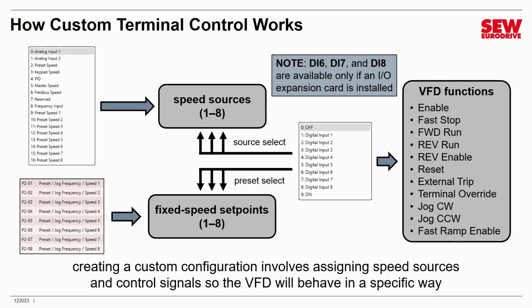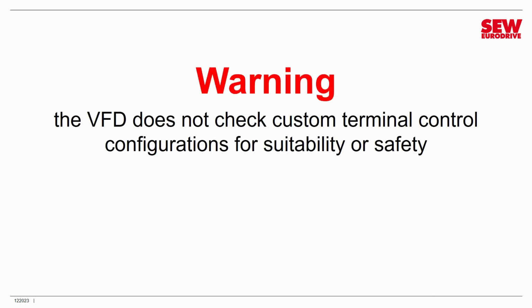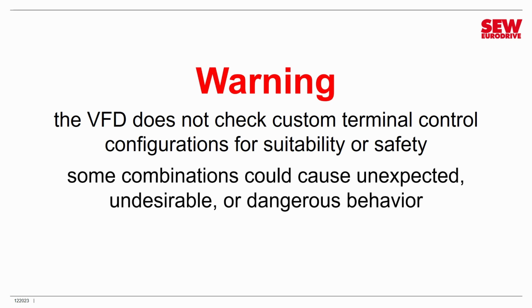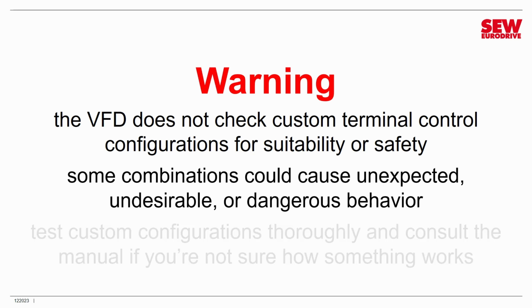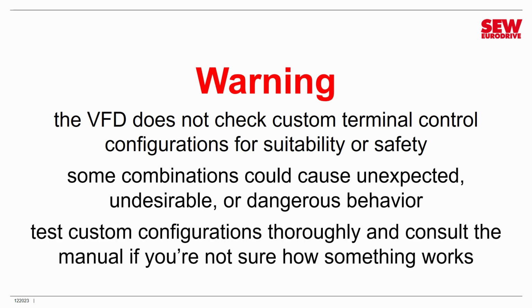And this is probably a good time to give you a little warning. The VFD does not check your setup for custom terminal control configurations as far as suitability or safety. It is totally possible to create a configuration that does something undesirable, unexpected, or even unsafe. So, test all custom configurations thoroughly, and if you're in any doubt about how something works, check the manual. So you have been warned.